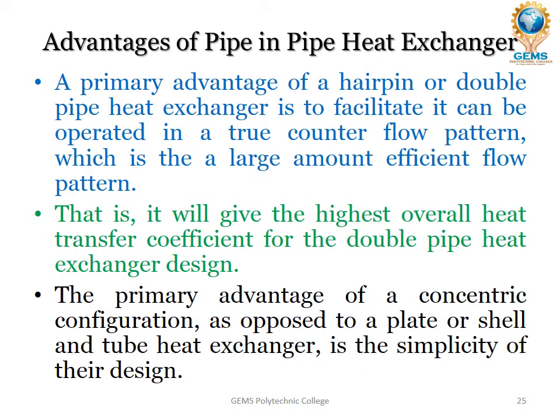Advantages of the pipe and pipe heat exchanger. A primary advantage of a hairpin or double pipe heat exchanger is that it can be operated in a true counter flow pattern, which is the most efficient flow pattern. That is, it will give the highest overall heat transfer coefficient for the double pipe heat exchanger design. The primary advantage of a concentric configuration as opposed to a plate or shell and tube heat exchanger is the simplicity of the design.